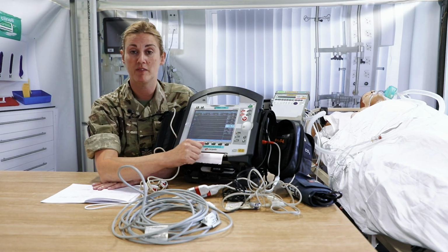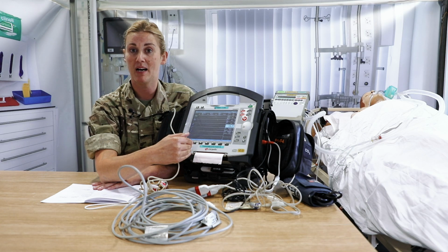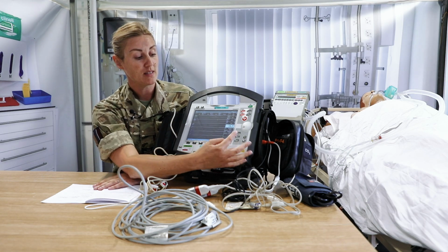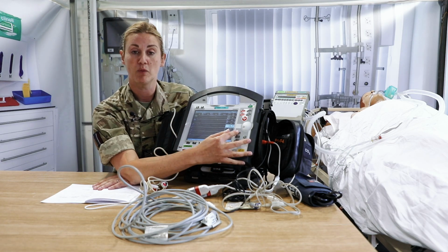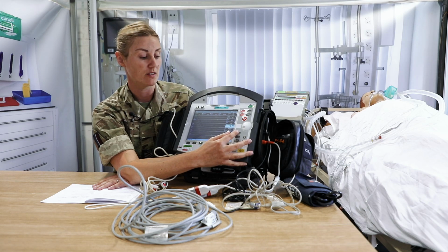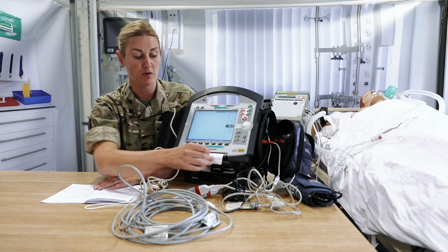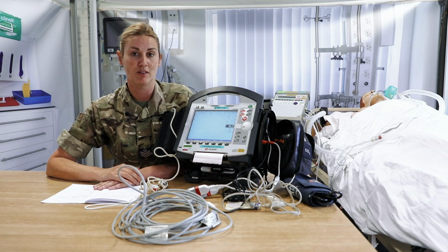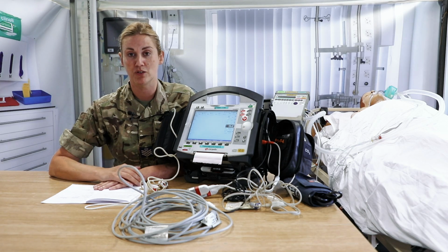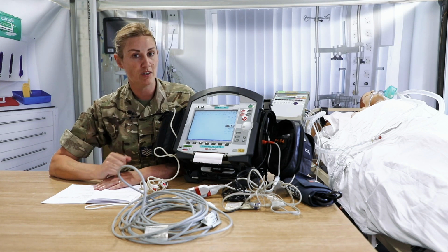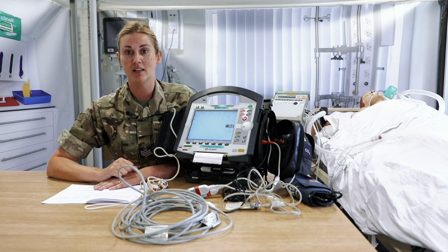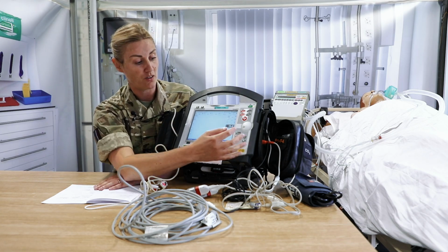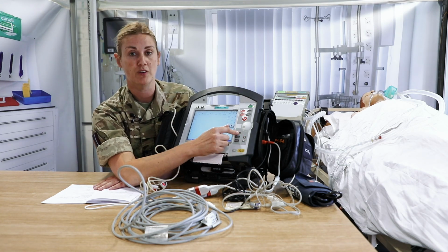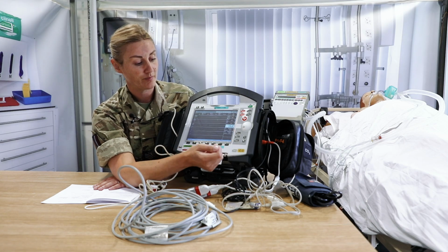We've already tested one of its functions to confirm that you go back into this safe screen, but the second function we're going to test is that we can change the color of the screen. So we're going to do that by pressing and holding the monitor button, and you'll see that there's a different, more of a daylight version of the screen. So this is how you're going to change that view between day and night if you need to in use. I'm going to return it back to that night view just because it's easier to see.